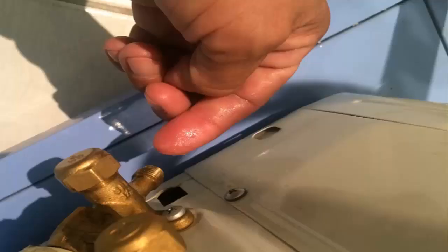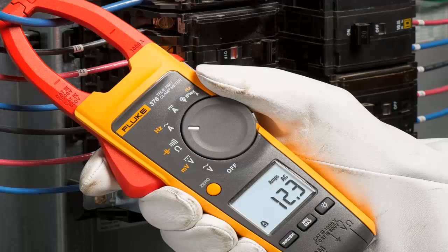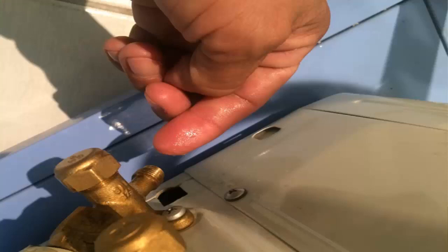2. Refrigerant leak. A recent refrigerant gas leak can cause the compressor to operate, but the unit does not cool properly. To fix this, it is necessary to check the refrigerant pressure. Furthermore, when there is less refrigerant, the amperage or current consumed by the compressor is lower than normal. You should look for and repair the leak. Look for oil stains to identify the leak, and use soapy water to find bubbles. Suspect any connections.